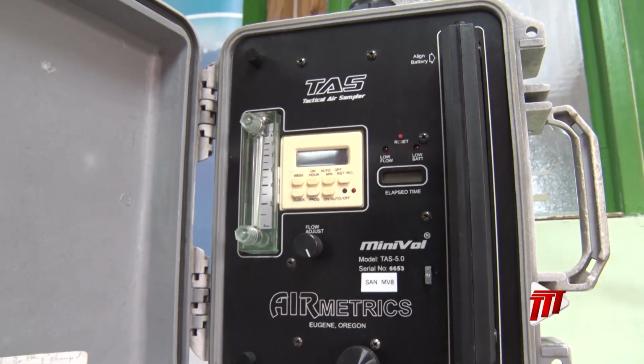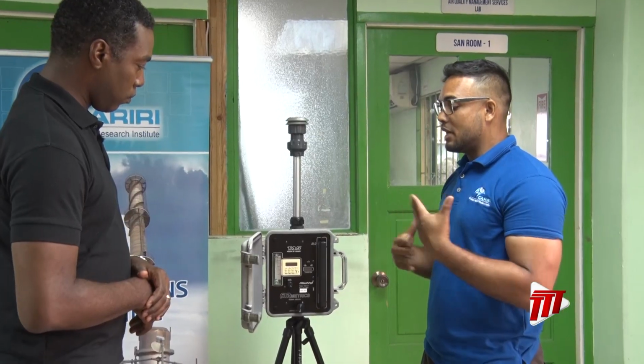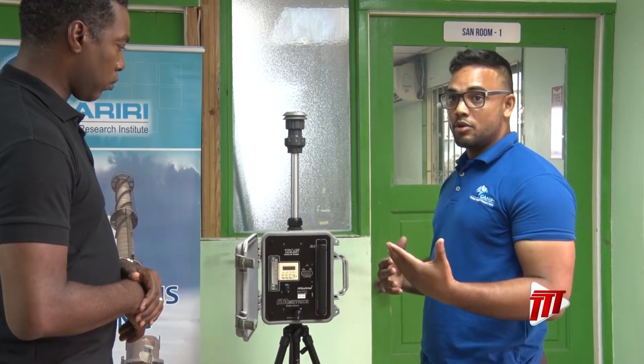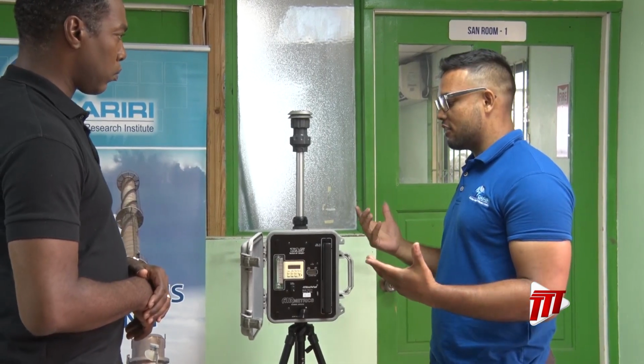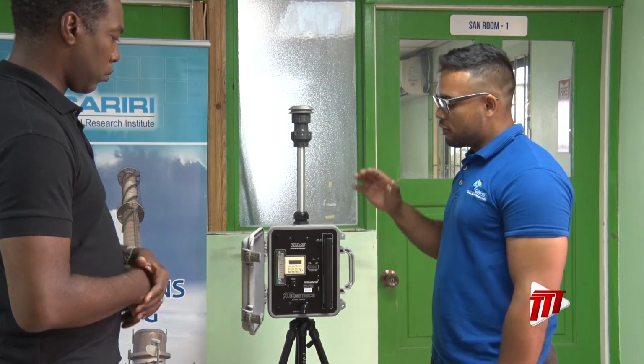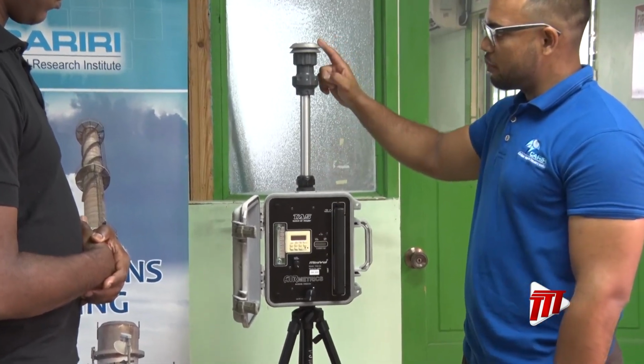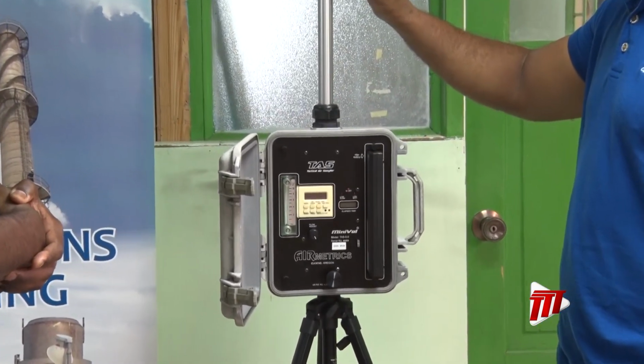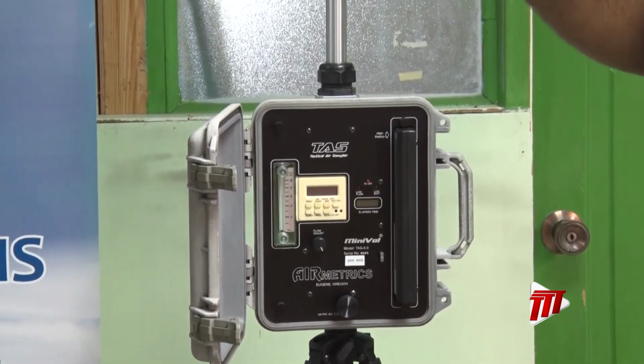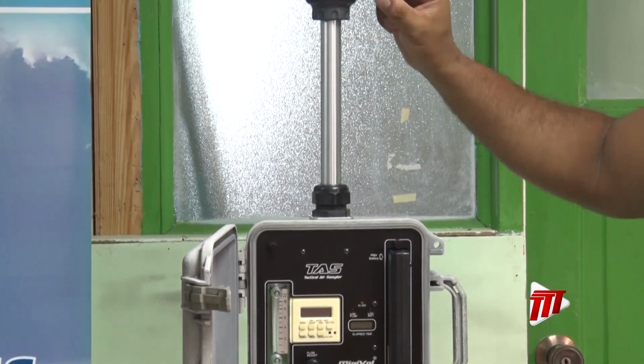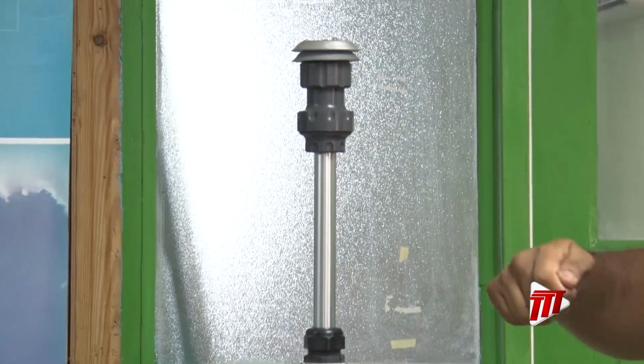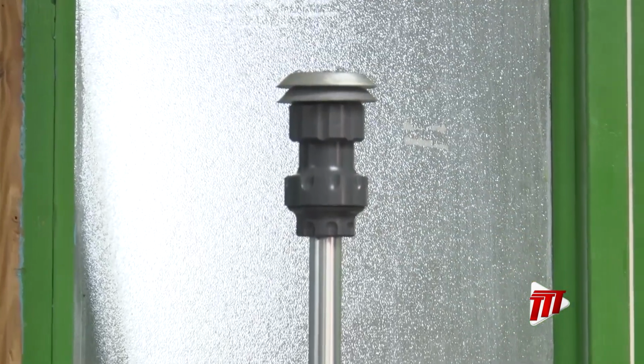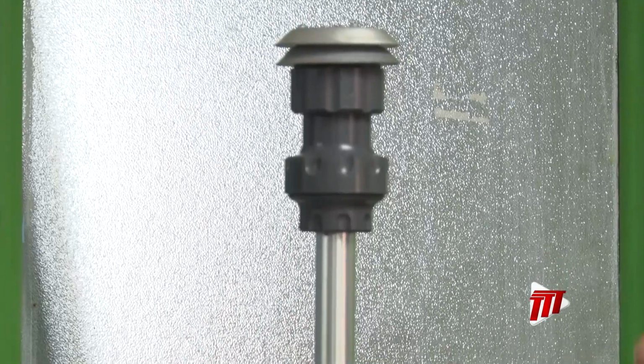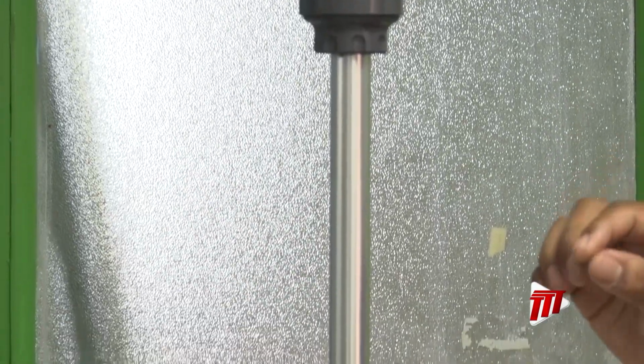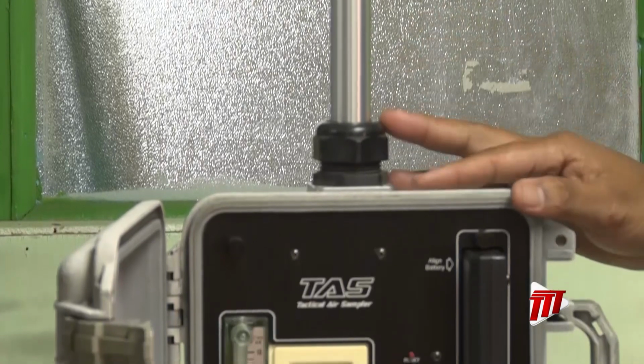So this is our MiniVol Tactical Air Sampler, tactical being named so in that it's portable. There's an internal battery, so you could use this anywhere in the field without the need for power from an extension cord. It's also weatherproof. Inside here, there's a pump. It pulls a sample of air through the top where there's a filter paper. As it pulls the sample of air, particulate matter is impacted on that filter paper, and then we take that back to the lab and we weigh it. With this piece of equipment, we can monitor TSP, what is referred to as PM2.5, PM10, and also total particulates.